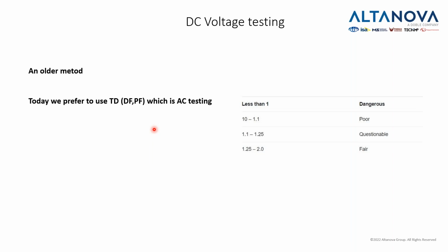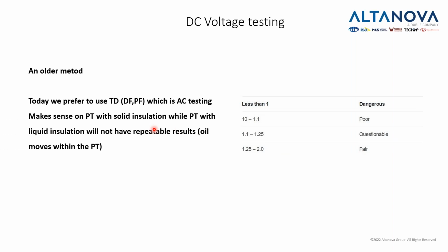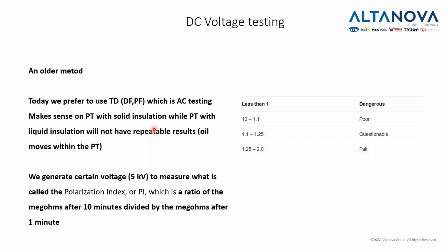Last test I'm going to mention is a DC voltage testing, which is an older method. Today we prefer to use tan delta, so power factor testing using an AC method. Basically what we do, we generate, let's say, 5 kilovolts. And by the way, let me mention that this test makes a lot more sense if we have a solid insulation, because if we have a liquid insulation, that liquid moves around the transformer, so we don't have a repeatable result. So even if we have the solid insulation, we might have issues with repeatability. Long story short, we're going to do a test which is called polarization index.